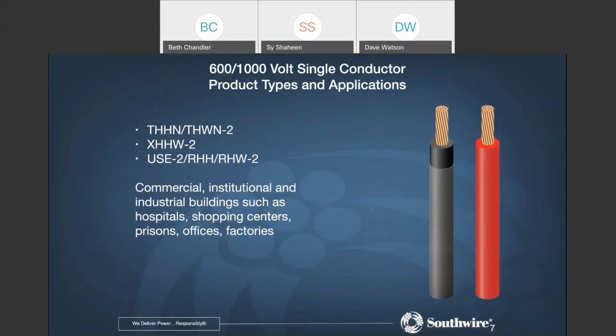So the single conductor product types that we'll look at today are the basic ones out there in the industry for use as a standard building wire conductor, recognized by the NEC, and used quite a bit in data centers. We have the THHN, THWN-2 conductors, which are thermoplastic. Then XHHW-2, a thermoset conductor. And the third one, the USE RHH-RHW, the triple rated product that is good for indoor-outdoor installations and can be installed direct burial, is also a thermoset product. Again, we'll go into each of these in a little more depth. The applications are the standard ones you would think of: commercial, institutional, industrial buildings, things like data centers.